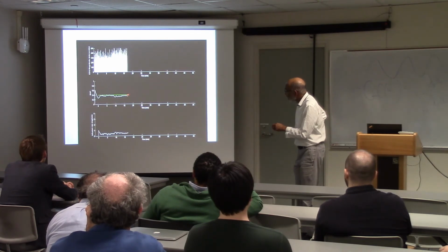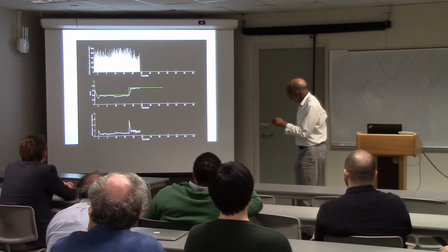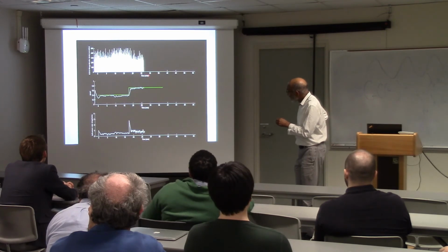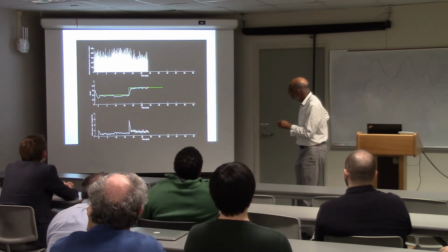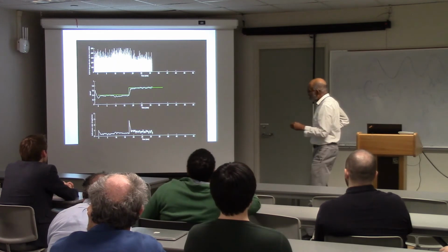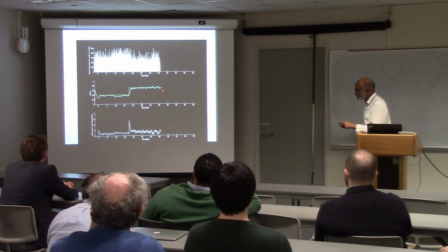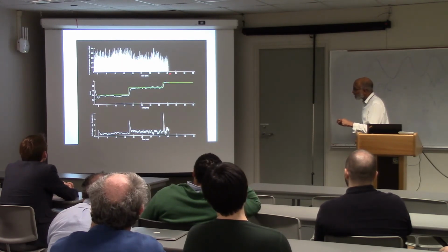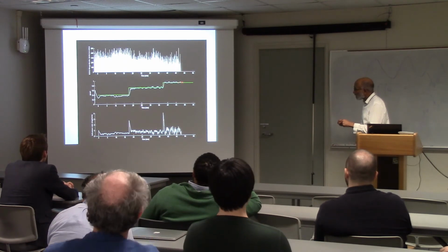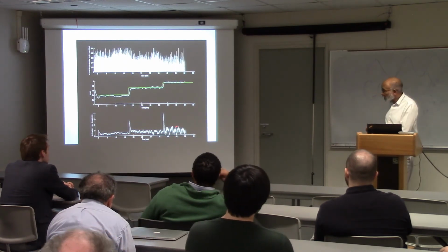Now we're going to take that to 0.7, so you need to make it 70% suppressed. The dynamics of the pump change in order to achieve that. And you see this getting a little bit lower here because now there's more suppression. This is actually following pretty well, and the time scale here is actually minutes. Now we go up to 0.9, so 90% suppressed, and you see this drops down even further. Most of the time it's suppressed, and you can see that it's pretty much on target. So the pump dynamics are different.